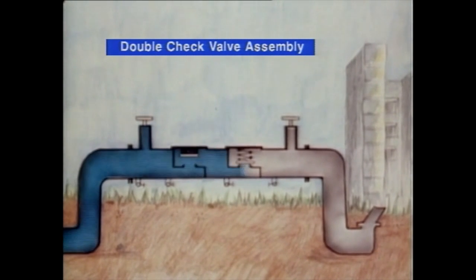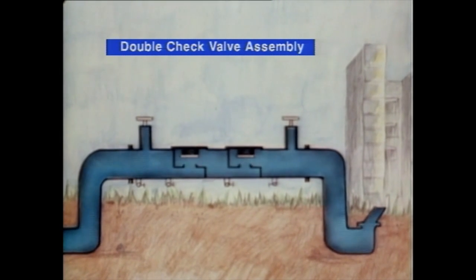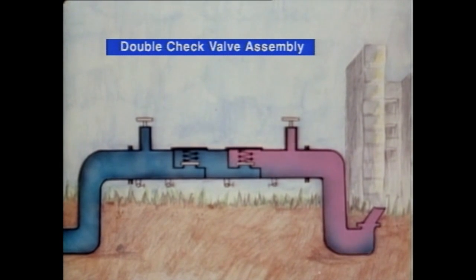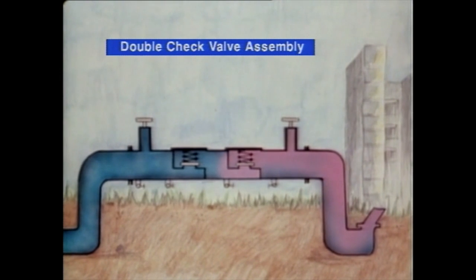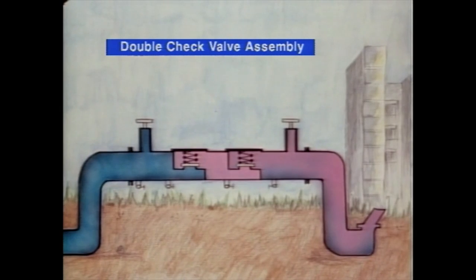But if the water became polluted in the building and the pressure from the booster pumps ever created the potential for backflow, the one-way check valves would be forced closed. Even in situations where one of the check valves was held open by sediment or rust particles caught on the valve seat, only a small amount of backflow could ever get through. A double-check valve assembly can only be used to protect against aesthetically objectionable materials — that is, not dangerous to our health.